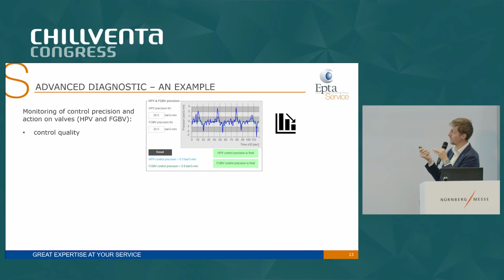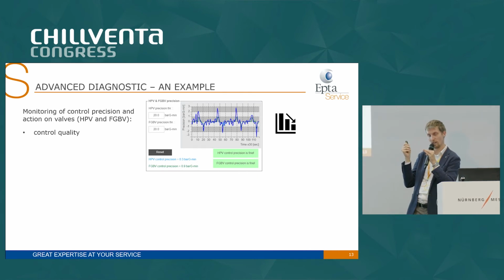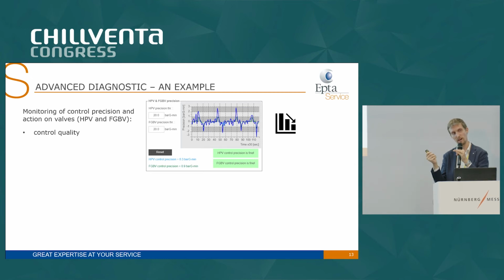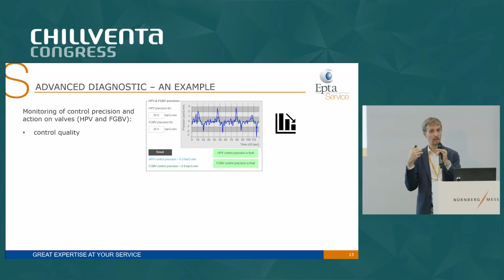So if we can say that the real variable, the process variable that we are measuring, the real gas cooler pressure, is close to its set point, we can say that we have a good control quality. So we are ensuring maximum efficiency of the system.